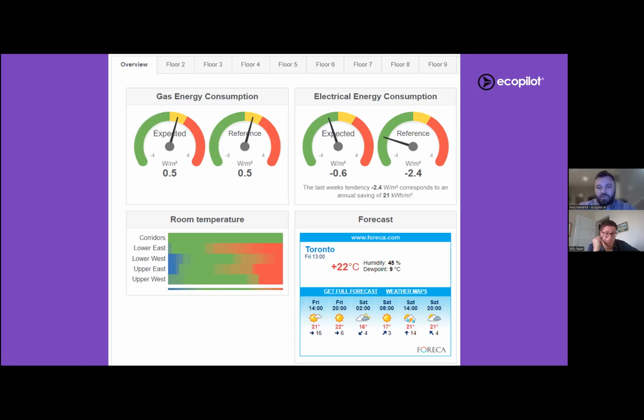On the bottom right is the weather forecast. We've done installs where the building operator is used to the building performing a certain way and gets a little perplexed—like, it's cold outside, but the boiler isn't ramping up and the ventilation isn't blowing harder. We include the weather forecast so you can see the temperature changing tomorrow; we're planning ahead because we know the building can withstand this temporary fluctuation. That's why it's on the dashboard.